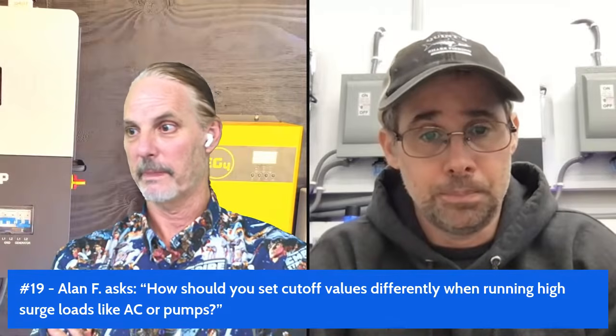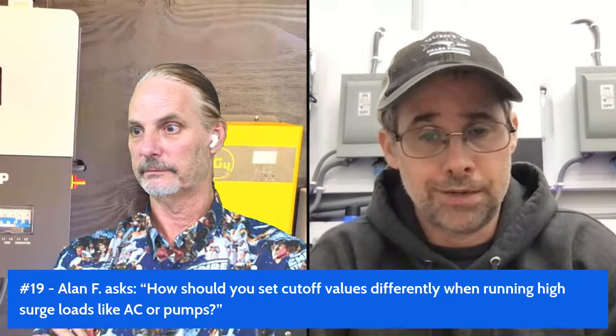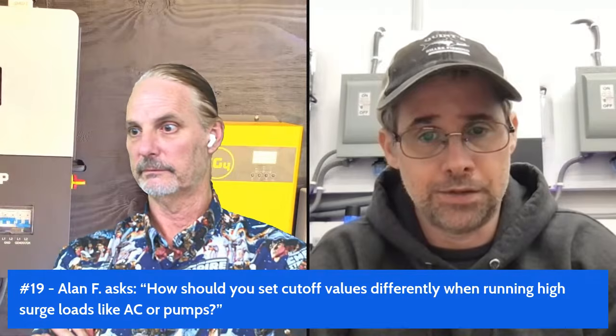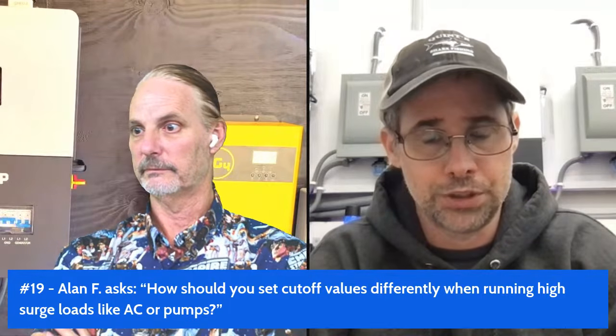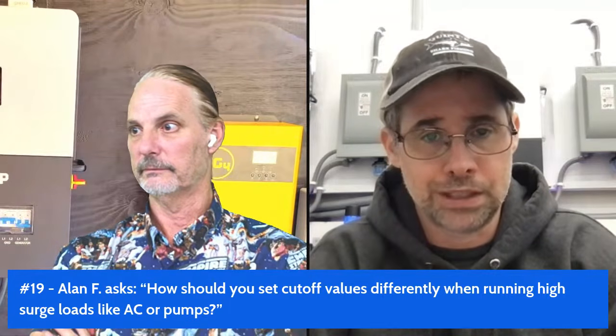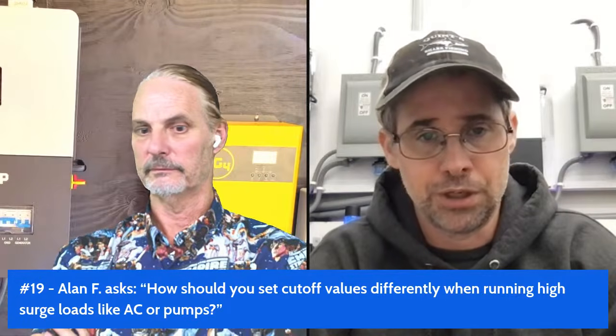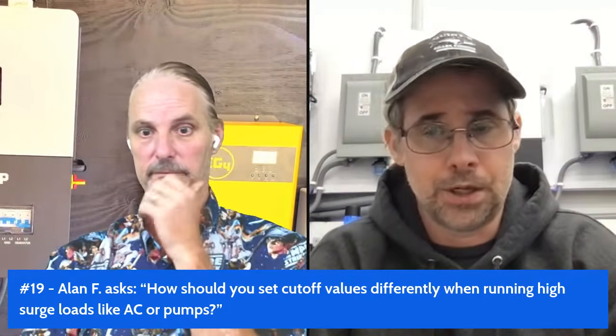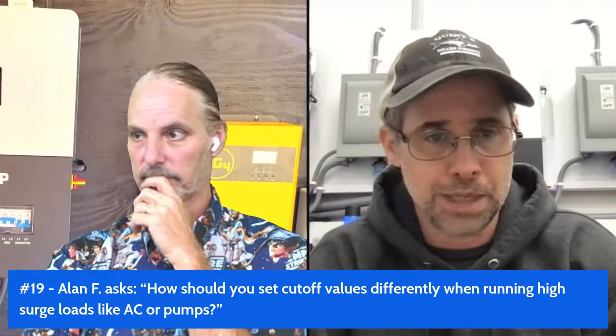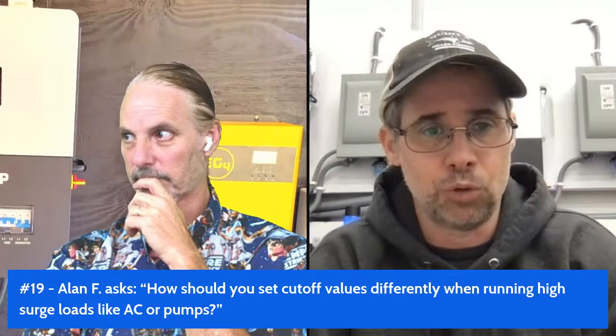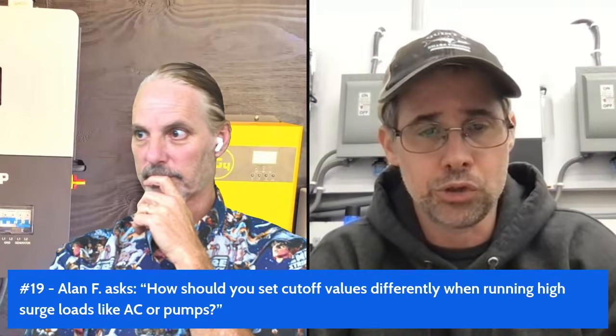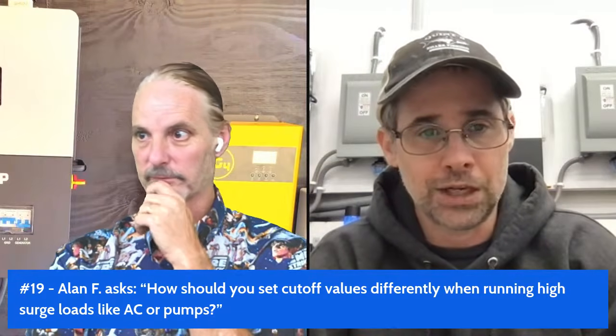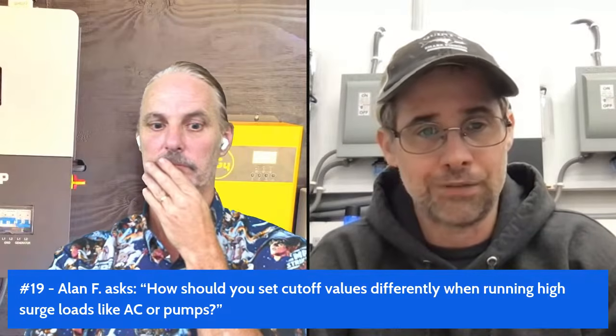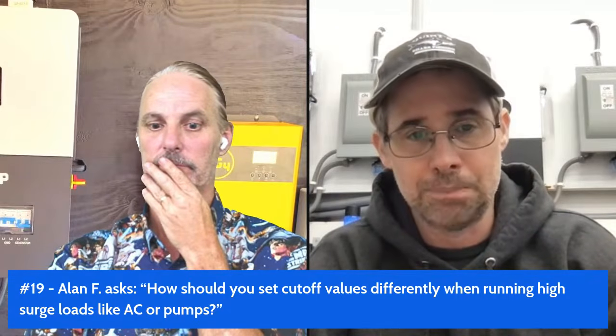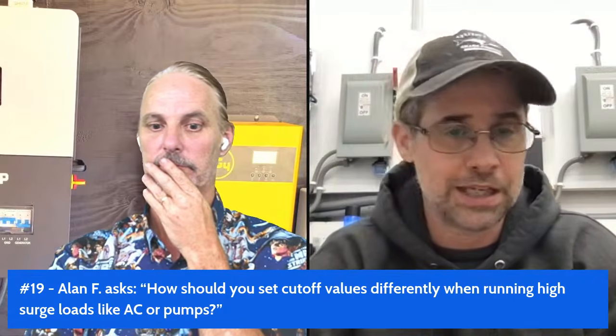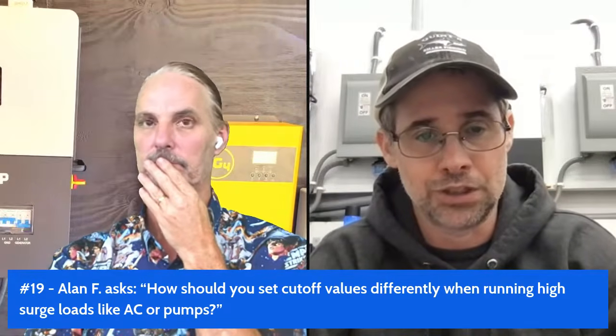If you have a smaller bank and large appliances like the ones you have there, you're going to have to compensate your shutoff voltage based on whether you have a big load or not. That might be why, like Matt's setup at 48 volts - you could be at 49 or 50 volts, but with only a couple of batteries, a big load quickly drops it down to 48 and trips the shutoff.